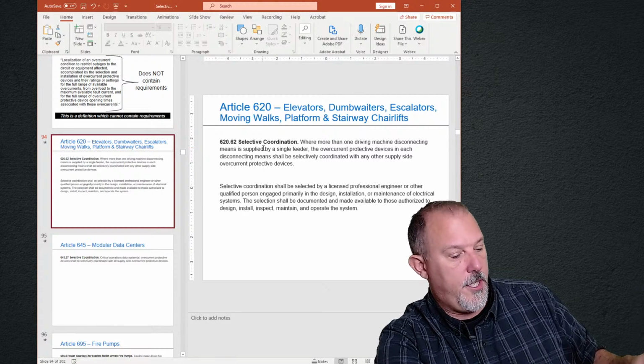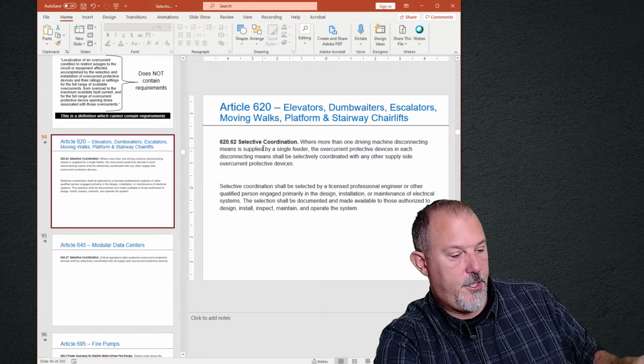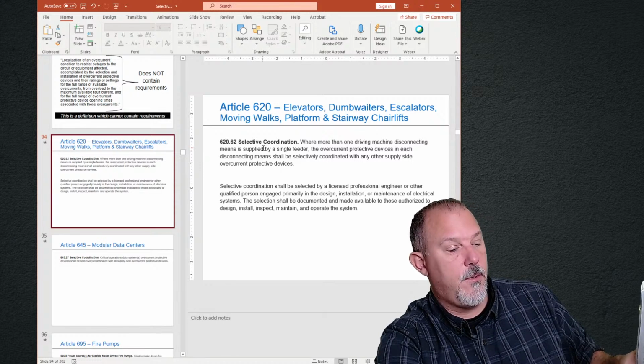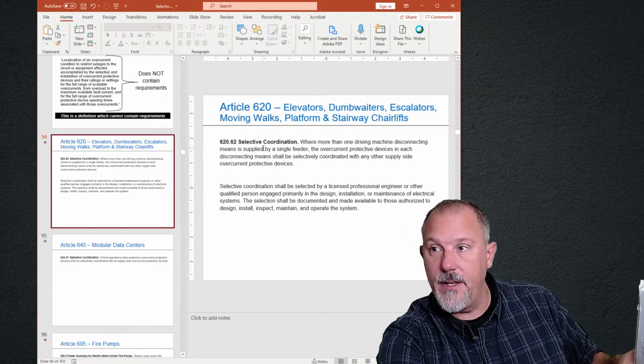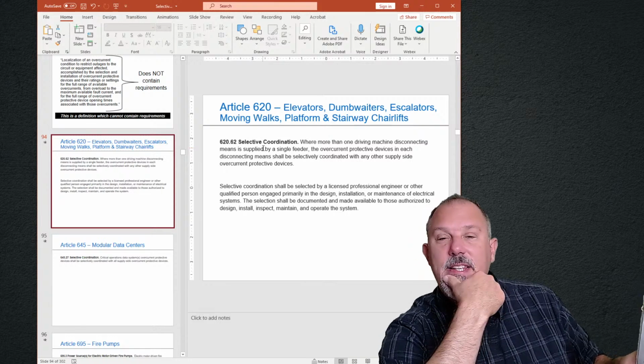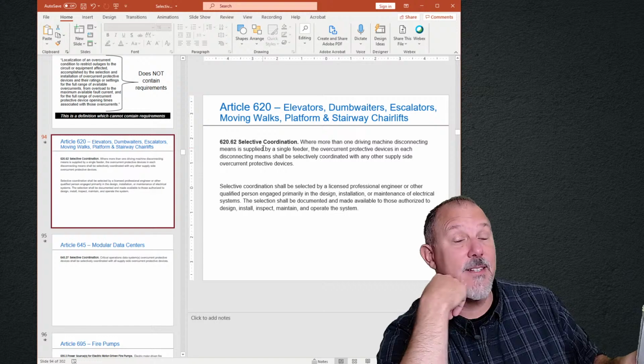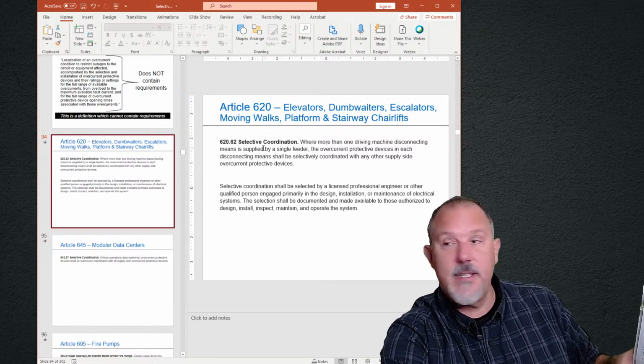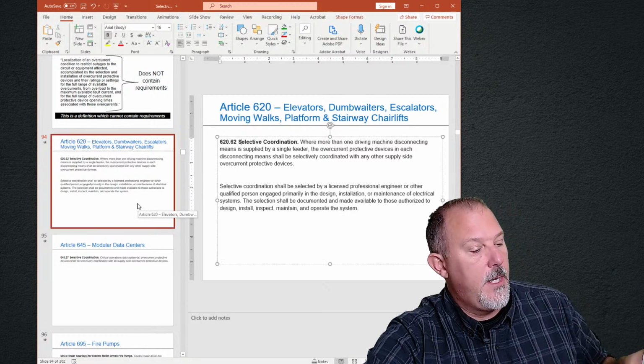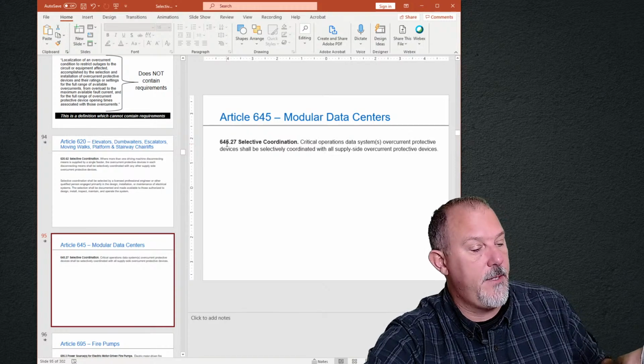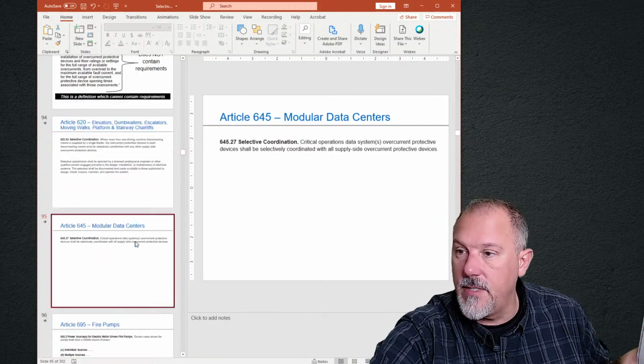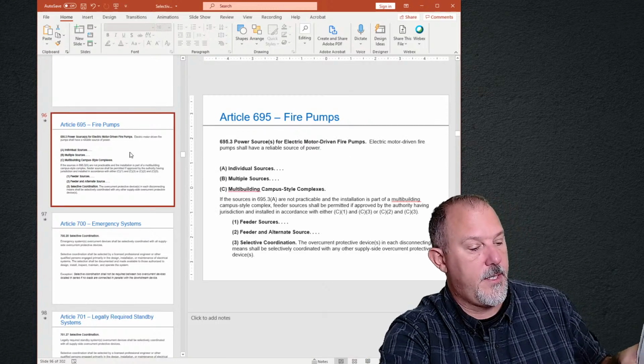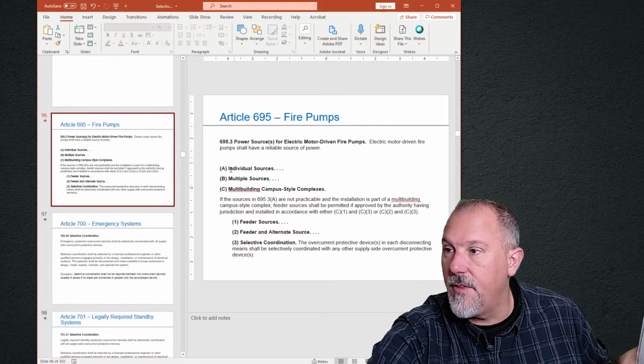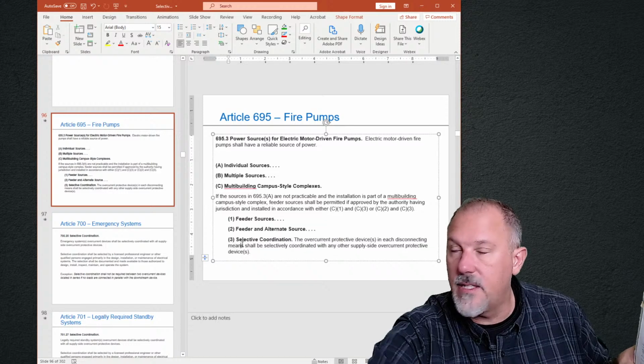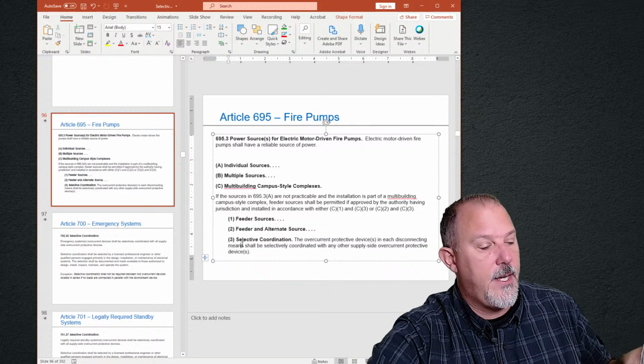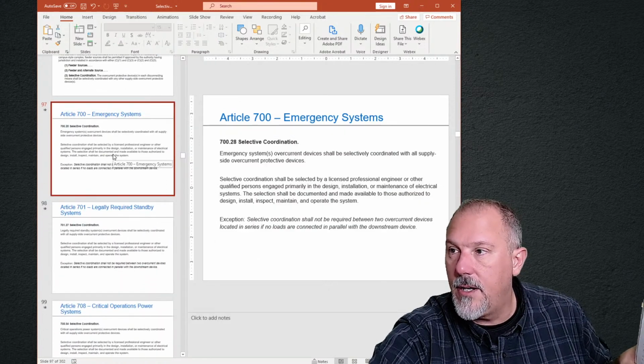Coordination, electrical systems, coordination, selective. Legally required, 701.32. Information technology, 645.27. Healthcare, 517.31(G) is not selective coordination. Selective is 620.62. There's your 620.62. 645, there's your 645.27. 695, so 645 is modular data centers. 695.3(C)(3), there it is. That's for fire pumps. 700.10(B), 700.10(B).